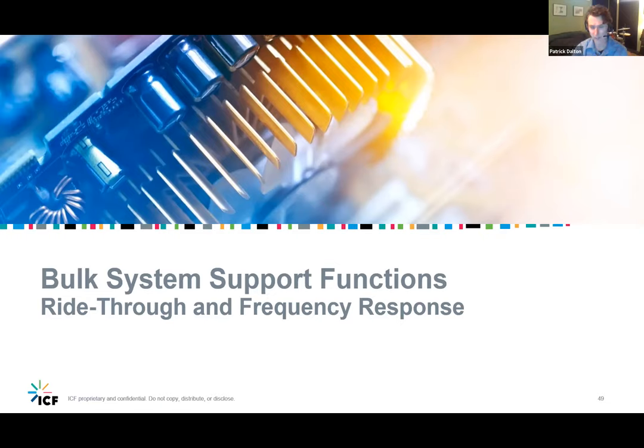The other reactive power functions, like fixed power factor, it's just really not a concern as much, because the DER reactive power response is decoupled from the grid. It's really only relying on the output of the generator at that time. And that's pretty similar to the watt var function as well. It's coupled to the generator output itself. Constant power factor is coupled to nothing. It's just a setting, it's a command.